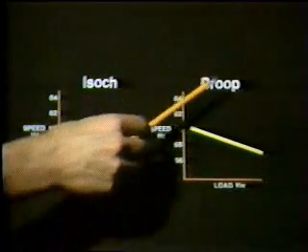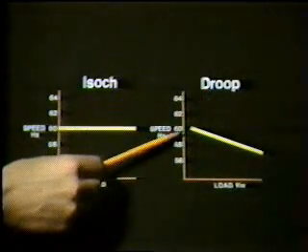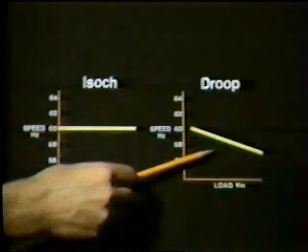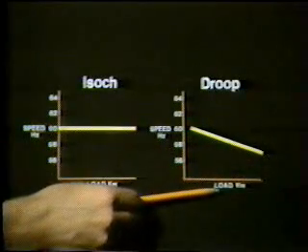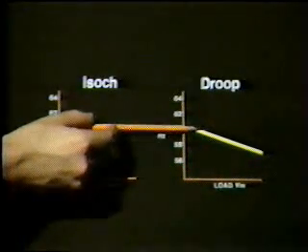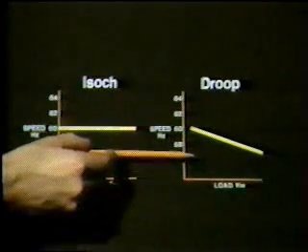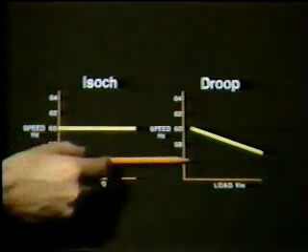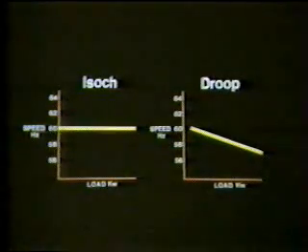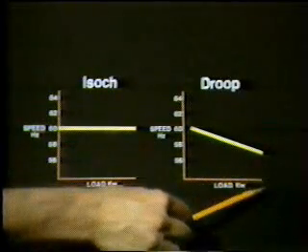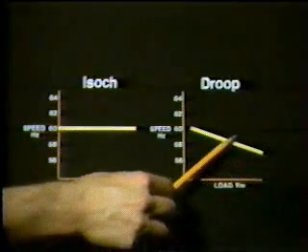You can see on this graph that when in the droop mode, engine speed will decrease as load is added. The engine speed will normally droop about 4% or to the amount adjusted on the governor as load is increased to full load, and the speed will increase as load is decreased. Load sharing is automatic in both isoch and droop mode.